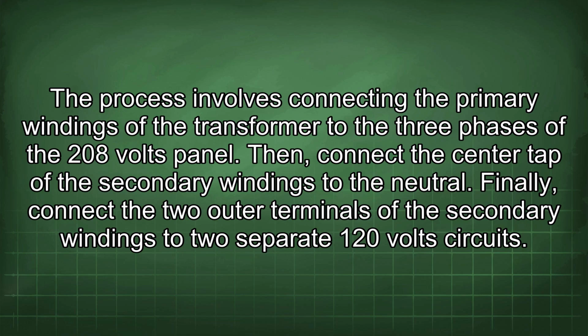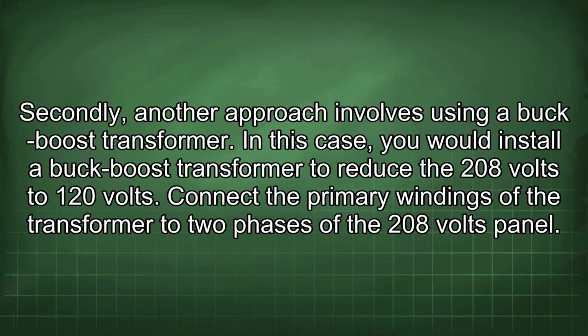Then connect the center tap of the secondary windings to the neutral. Finally, connect the two outer terminals of the secondary windings to two separate 120 volts circuits. Secondly, another approach involves using a buck-boost transformer. In this case, you would install a buck-boost transformer to reduce the 208 volts to 120 volts.